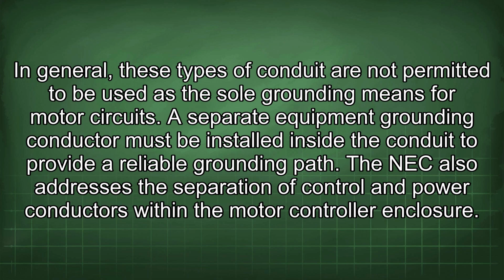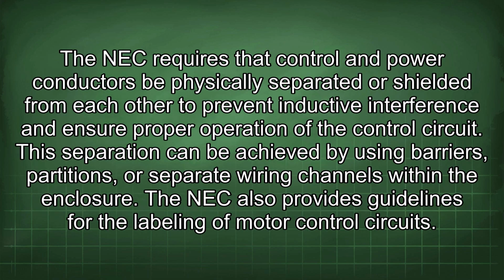The NEC also addresses the separation of control and power conductors within the motor controller enclosure. The NEC requires that control and power conductors be physically separated or shielded from each other to prevent inductive interference and ensure proper operation of the control circuit. This separation can be achieved by using barriers, partitions, or separate wiring channels within the enclosure.